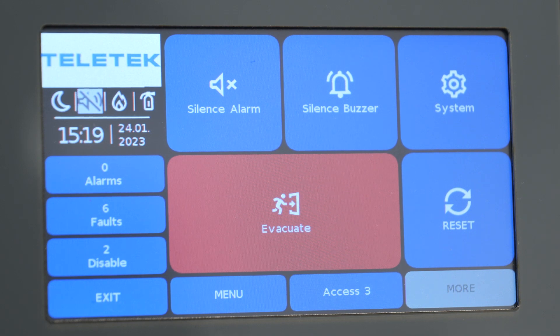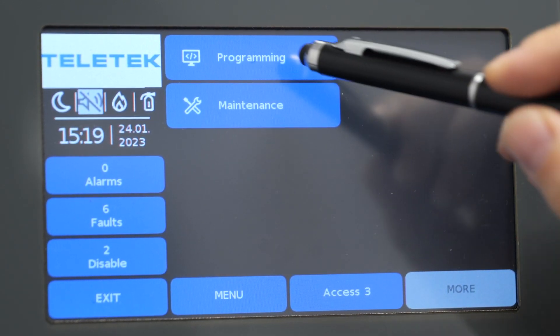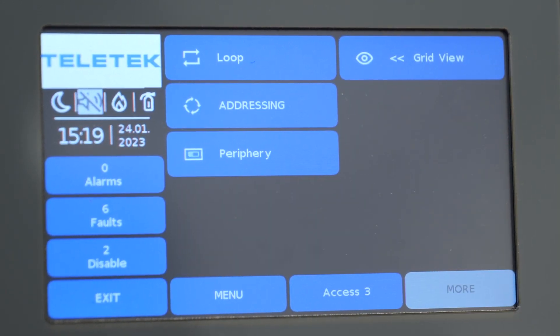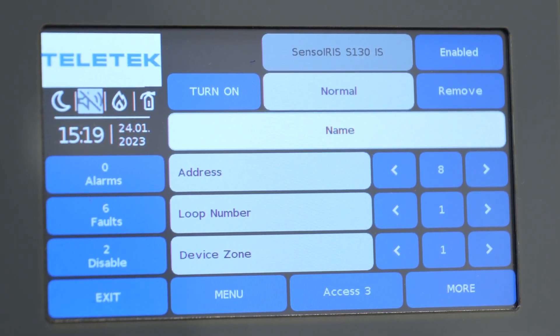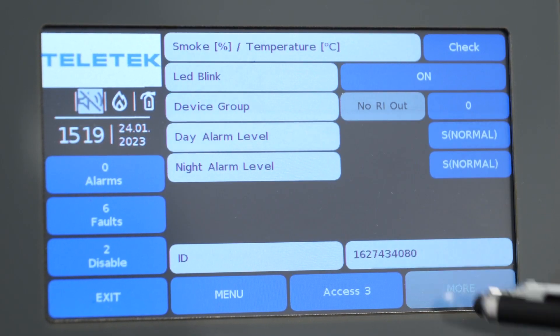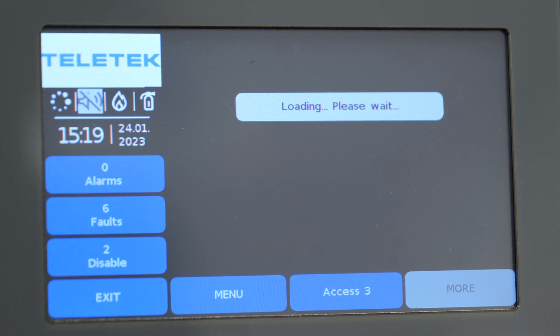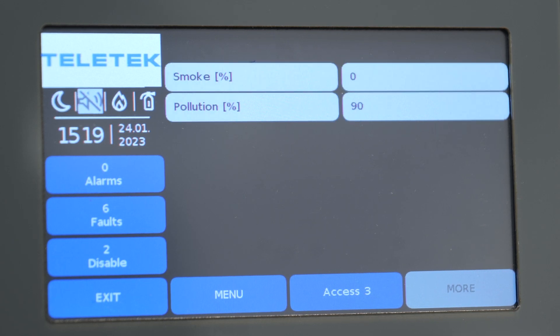After you clean the detector and place it on the loop, the pollution level readings will show the last recorded value which is before the cleaning. To update this number, the detector must be connected to the loop and working for at least 30 minutes.